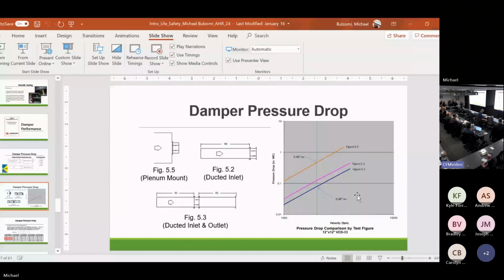If I just look at purely the size, first of all, this is the most common: ducted in, ducted out, 5 diameters of straight duct downstream, 6 upstream. How many jobs actually have that? Zero. But that's how we test it. I've got a plenum mount, and then a ducted inlet like a grille mount, right? If you're looking at this line, and this is your application, what's your difference? It's 5.3, the lowest pressure drop. The same velocity for 5.5, it's exponentially higher.